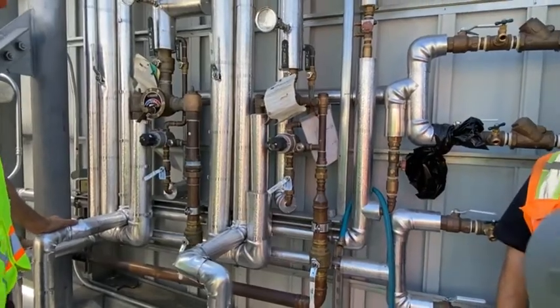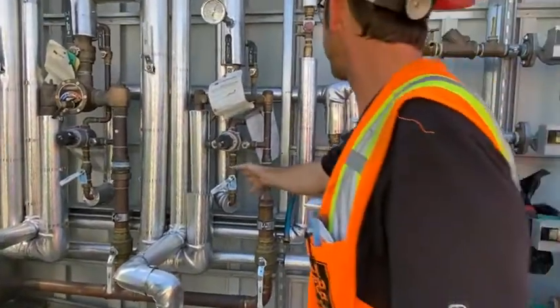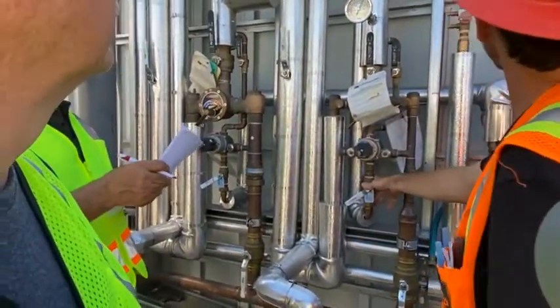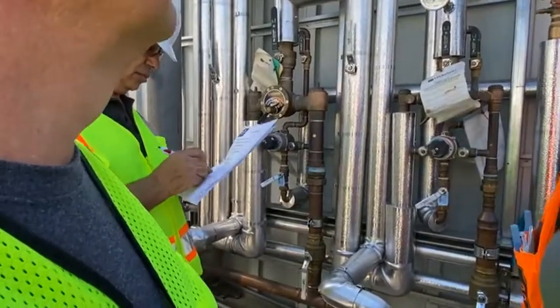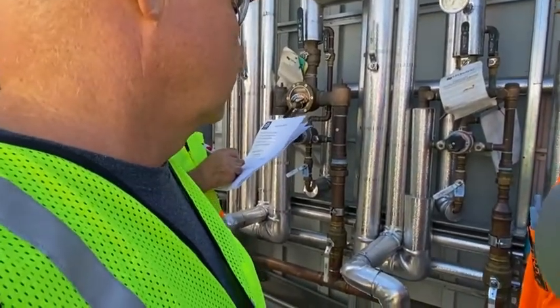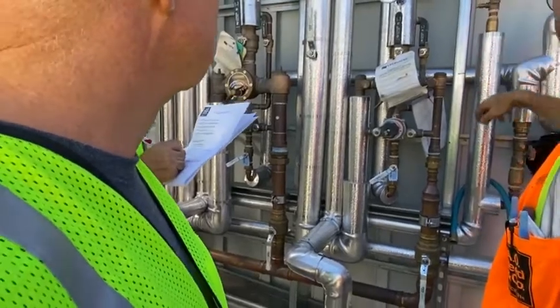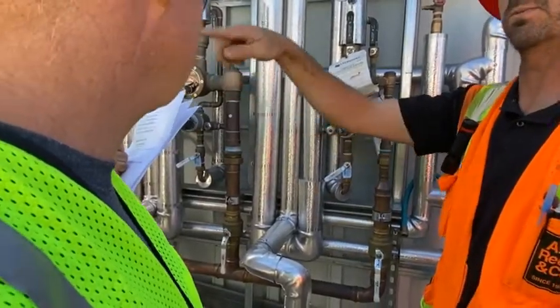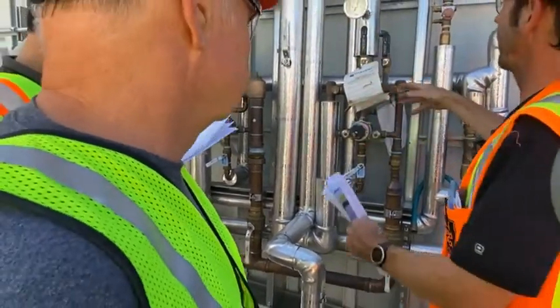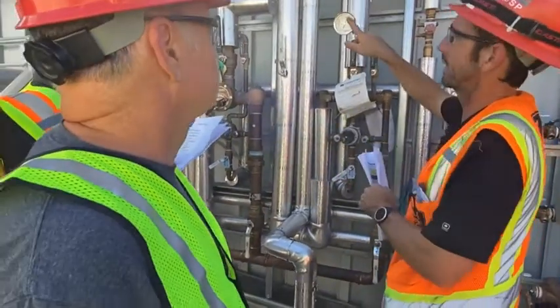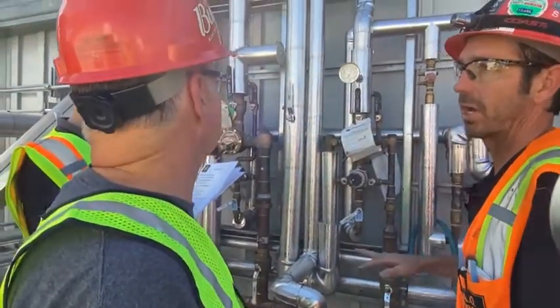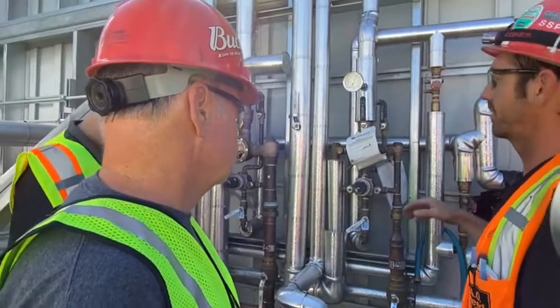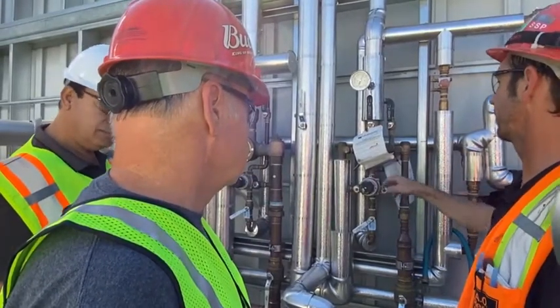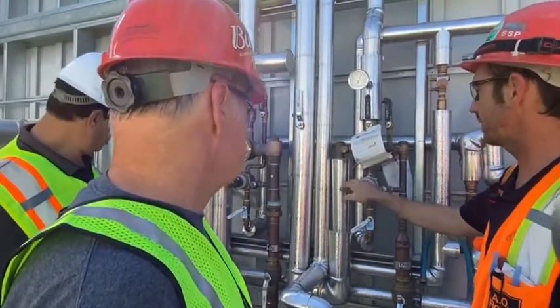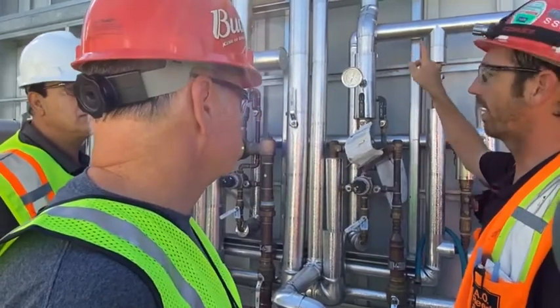This is the low temperature return right here. Make sure I'm showing you the right one. That's going to be off of our non-kitchen return pump. What we do is we pump just a little bit of the water through the high temperature loop, which is through the tank, and then that will blend together and give us a good 120 leaving set point during no-use demand. While there's demand and usage, it'll just flow through. The regulator itself will modulate to mix the hot and cold and go out at 120.